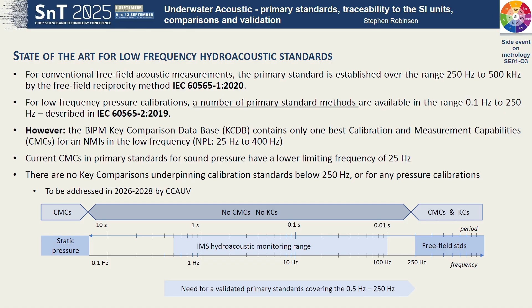So before I describe a couple of the calibration methods that are used, a little bit about this pressure versus free field. What we really want is a free field calibration, because a hydrophone or microphone is normally used to measure sound waves, which are emitted by some source, propagate through a medium, and are received by a receptor, whether it be your ears or a microphone or a hydrophone. It's very difficult to do these kinds of free field calibrations at very low frequencies. And so what is typically done is we do something called a pressure calibration.